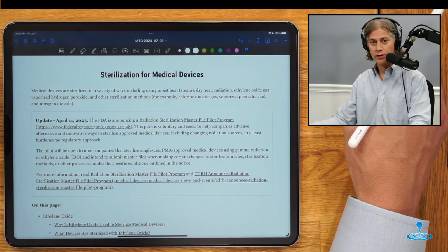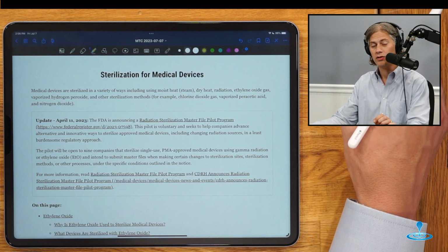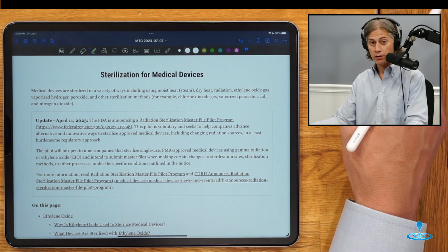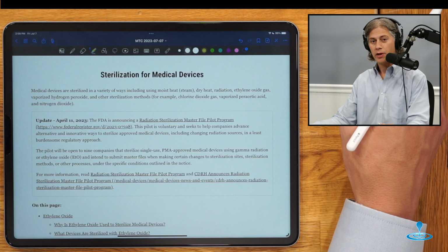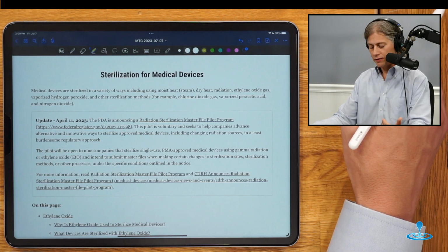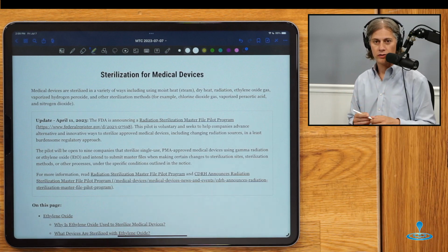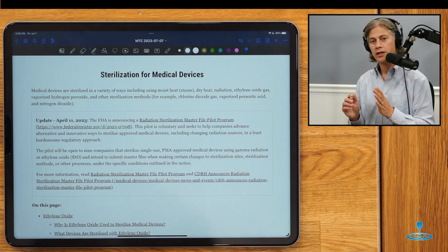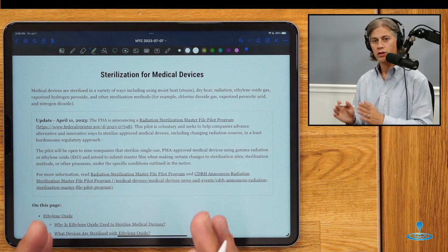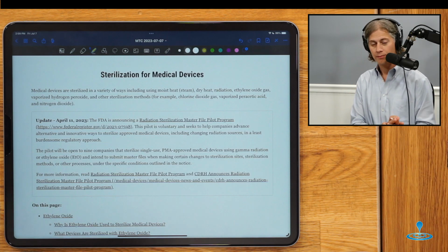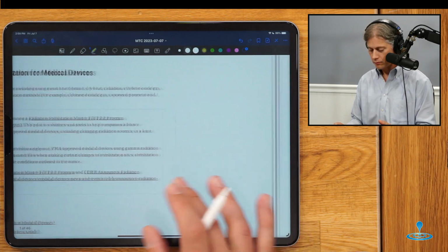So let's say you're a manufacturer and you're using a traditional ethylene oxide cycle and it becomes unavailable to you and you just can't get your product out there. Are you dead in the water? Do you have to stop? Do you have to revalidate your entire product through some other method and then resubmit to FDA for clearance? This is where the sterilization master file comes in. Because if there's a master file that really has characterized this new sterilization method, FDA is trying to make it possible that certain devices can switch over and not have to resubmit. So that's really, really good news for companies that might find themselves in that space.